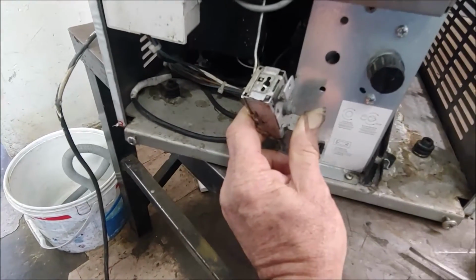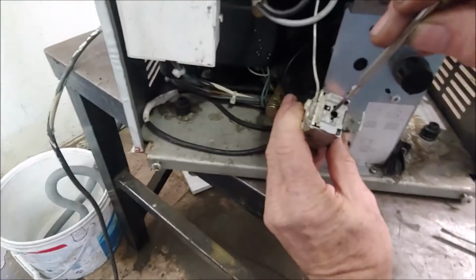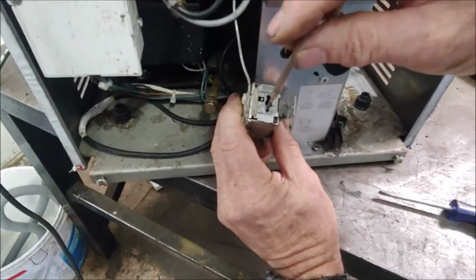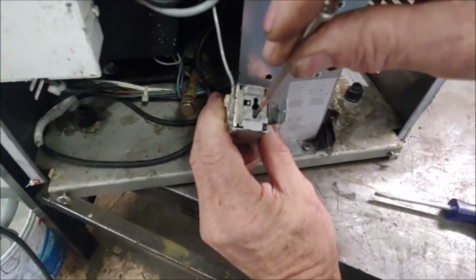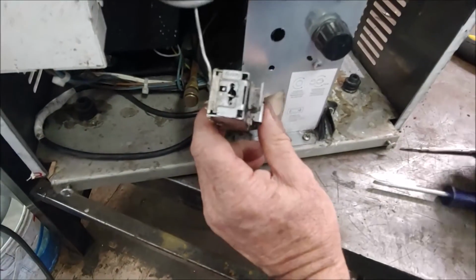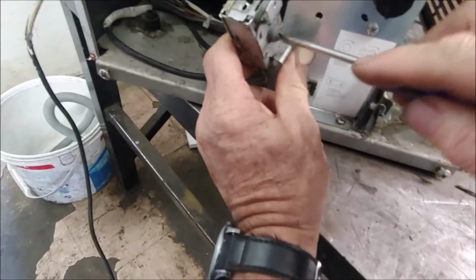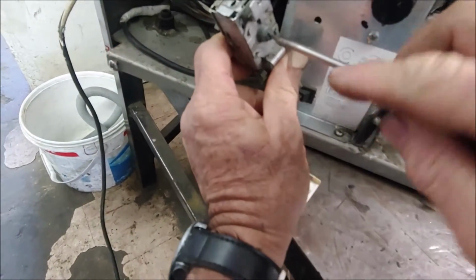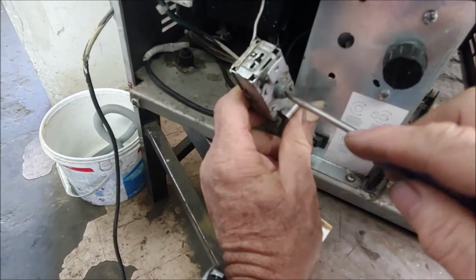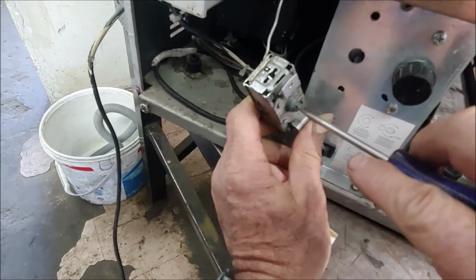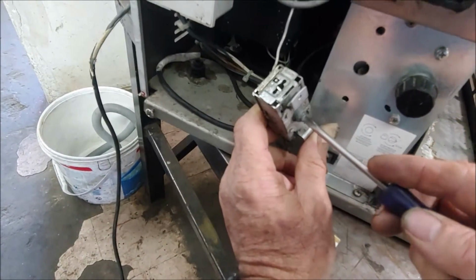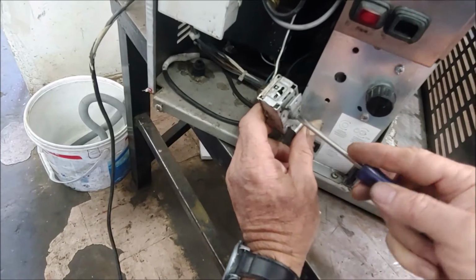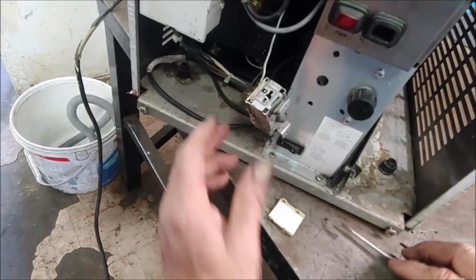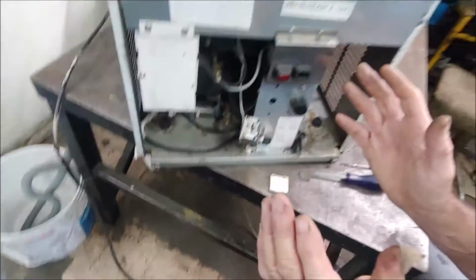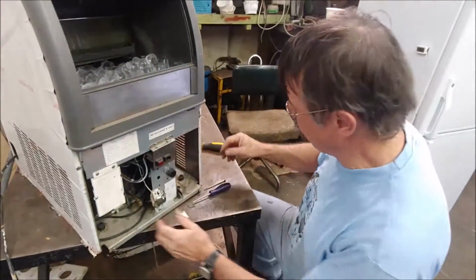Now to get it to the middle of the range, you adjust a little screw. You turn it in or out, and what you're doing is making the thermostat colder and warmer. Once you've got that clicking sound of the contacts opening and closing in the middle of the range - there's probably about a third of a turn now that I have to turn in order to get that clicking sound in the middle. That distance between the on and off we call the differential.